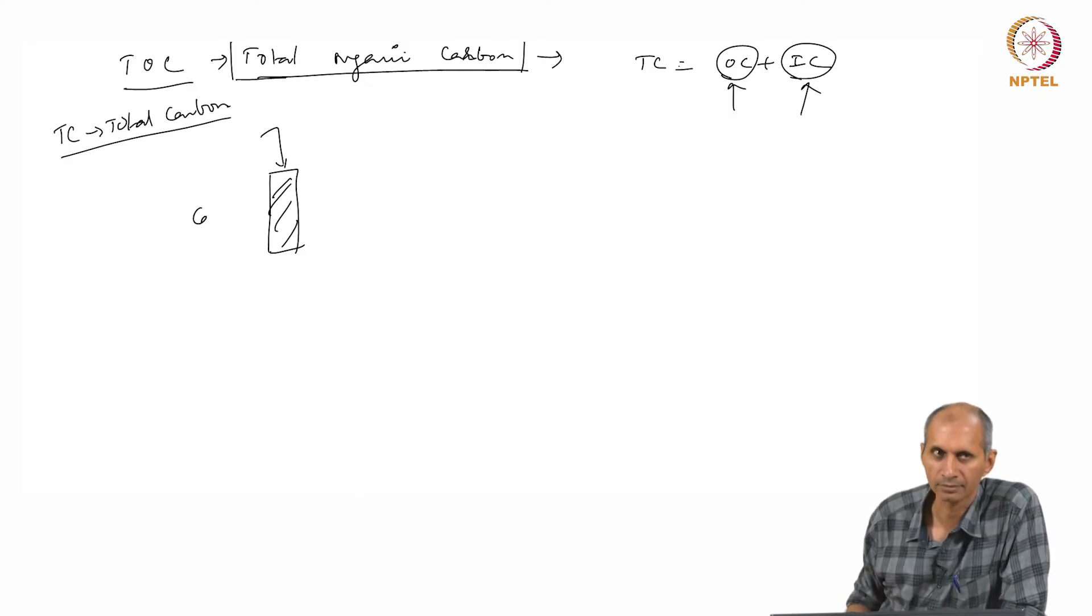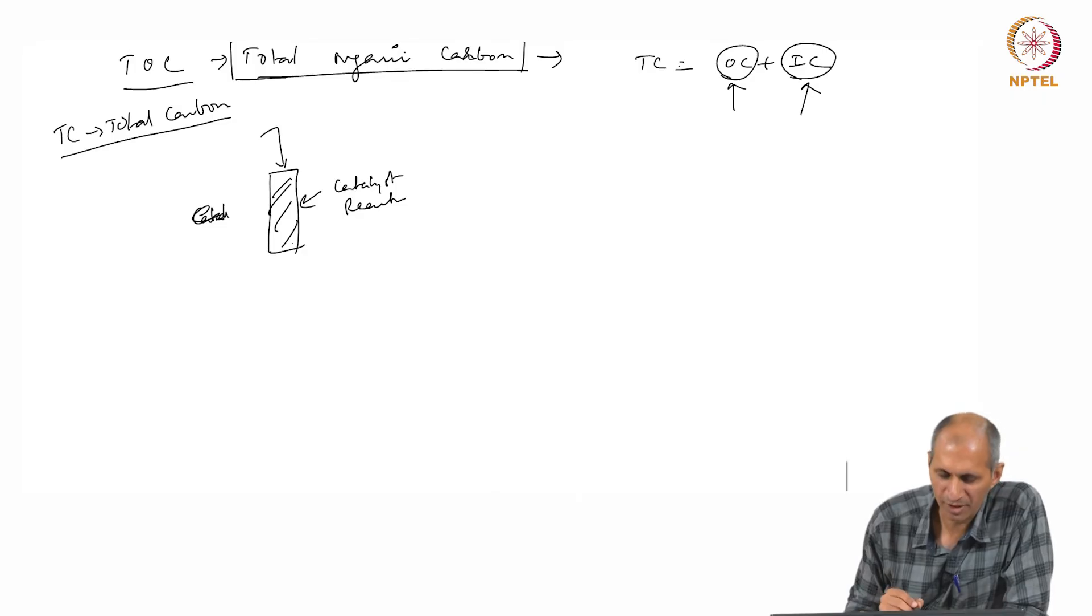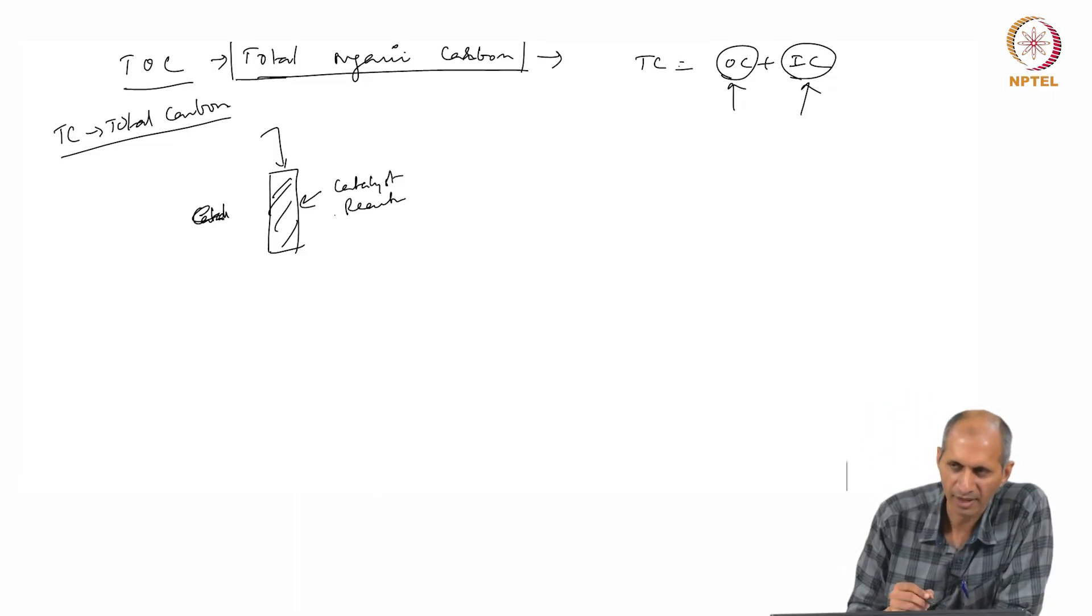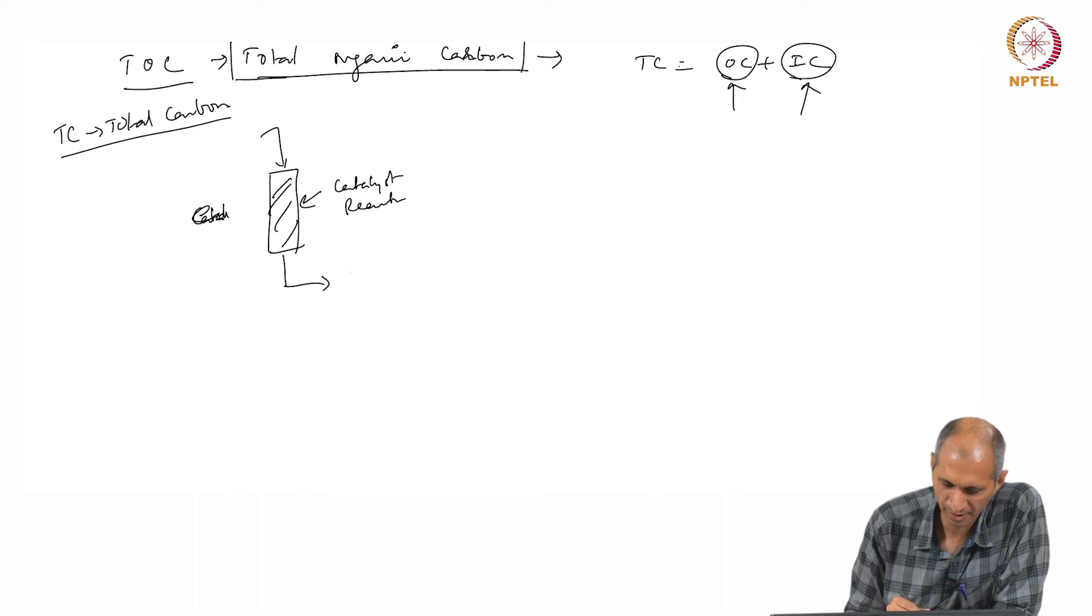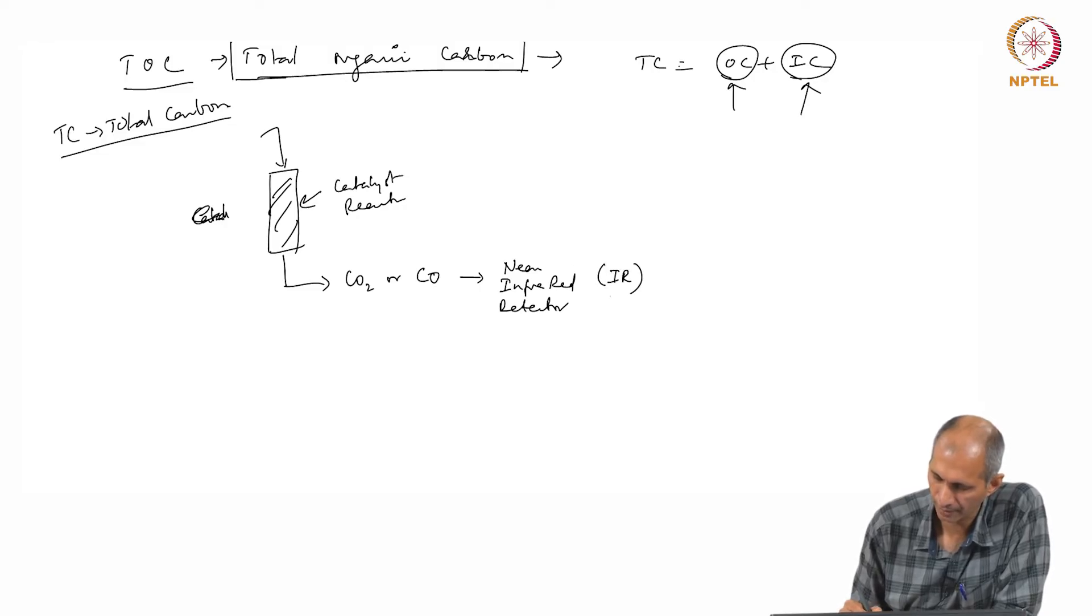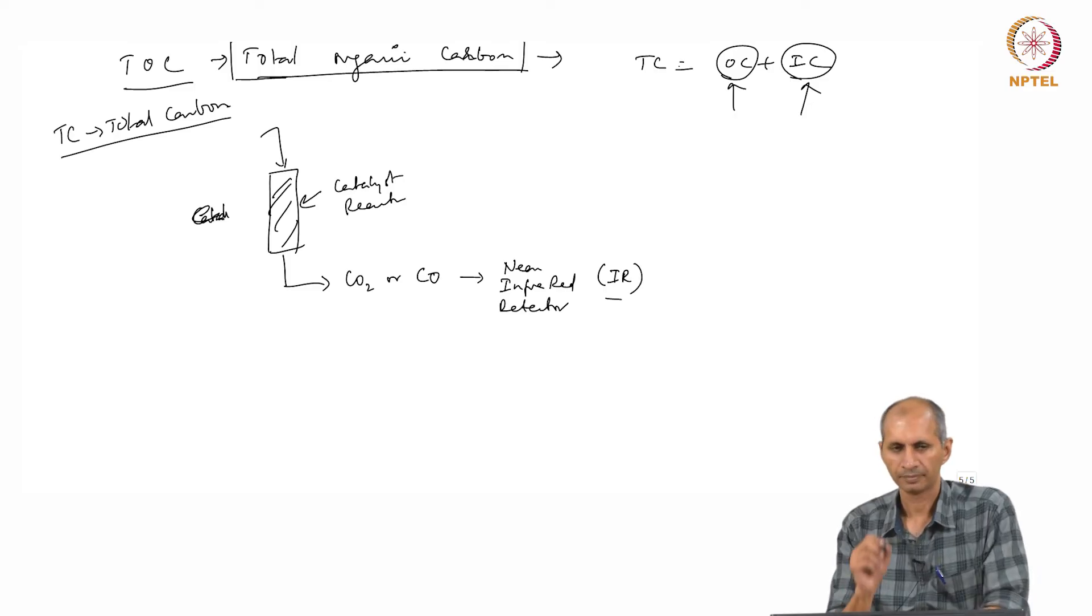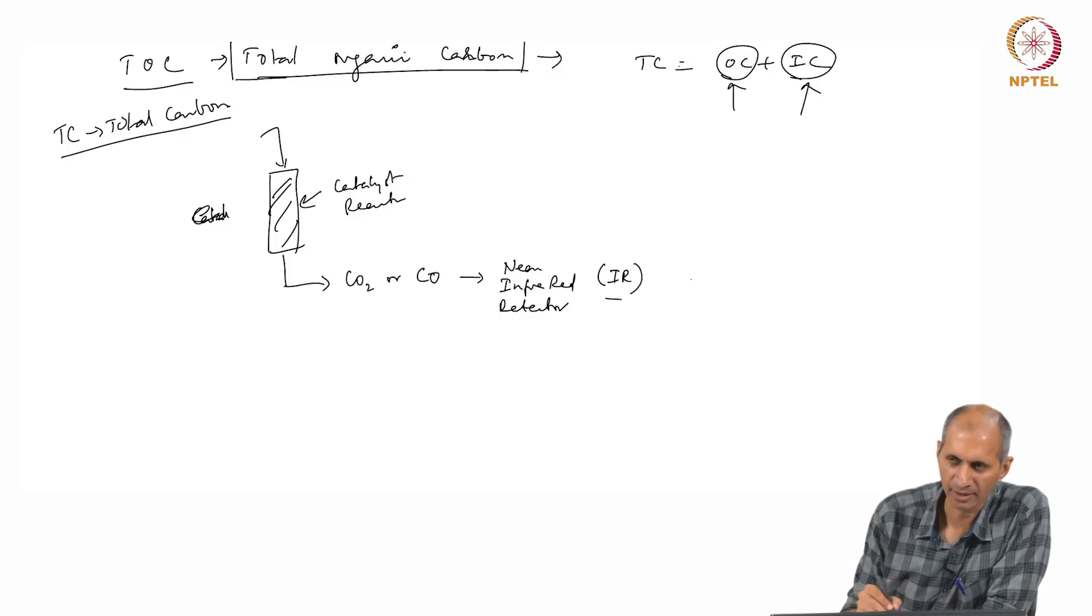The organic carbon—the water is added to a reactor which basically does oxidation. All the carbon is oxidized—catalytic oxidation at high temperature. It will release carbon dioxide or carbon monoxide, and this is measured using a near infrared detector, IR detector.